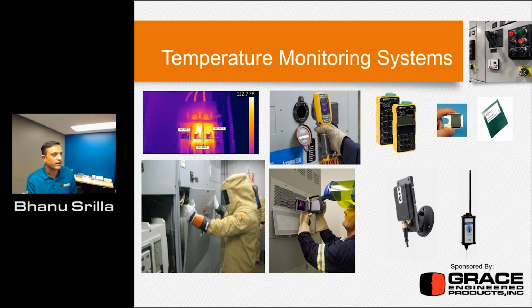And then what I'm showing to the right here are some of those remote monitoring devices. The one that's yellow here, I'm just pointing on the screen, it's basically the hotspot monitor, which is our GraceSense product, temperature monitoring device. The advantage of this device is basically you connect this using a non-contact fiber optic technology, so you can monitor the temperature measurements remotely. So in this case, you don't need to even have the close proximity of the gear, right? You don't need to expose your persons in terms of the closed door in the same room as well. You can have someone sitting in their SCADA room and then monitoring this temperature.